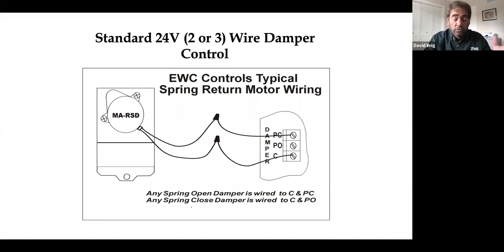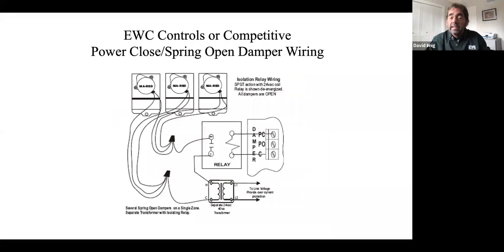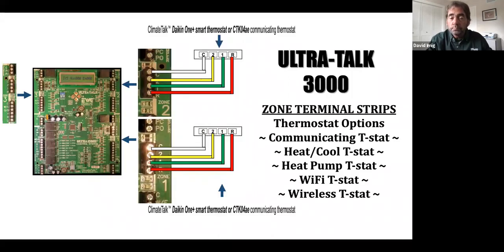That's what gives you the ability to tie in up to 18. If I come to a job site where I'm using the existing dampers and they happen to be spring dampers, as long as I have 1, I can tie directly per zone. If I would happen to have more than 1, you cannot tie all 3 into those zone terminals. You need to use a third-party relay and transformer, such as you see in the wiring diagram, to power those dampers prior to connecting to the terminal.